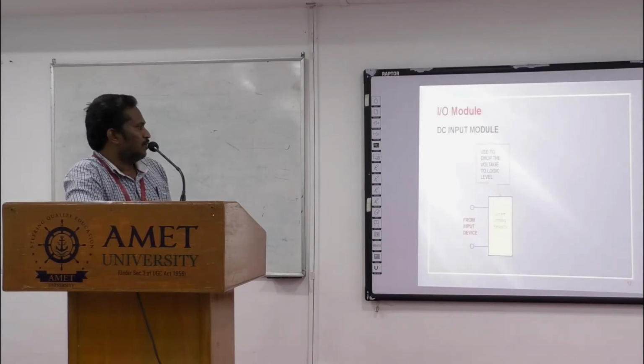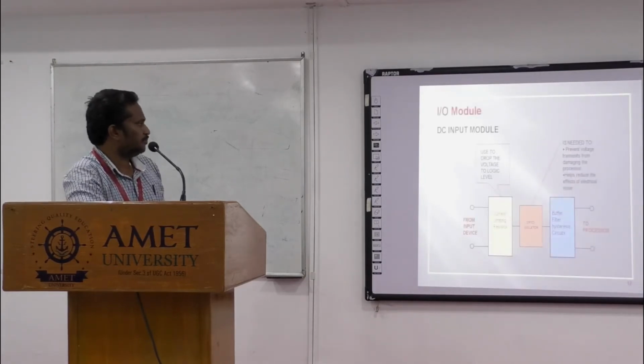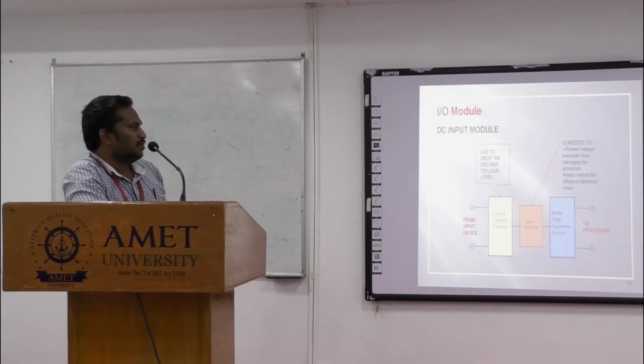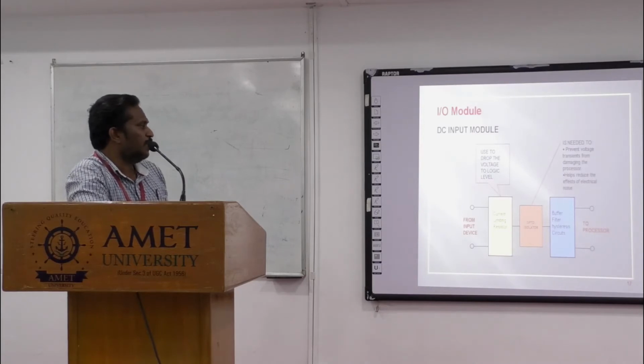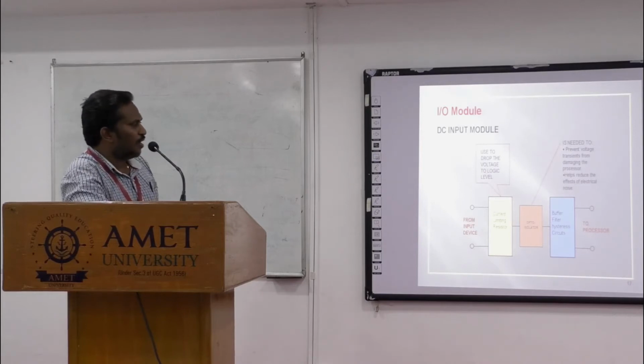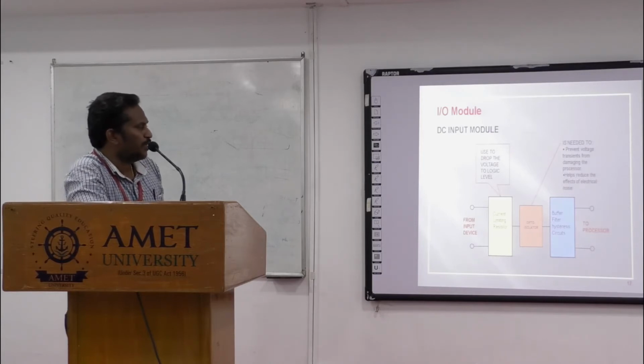DC input module. The DC input module will have three sections: a current limiting resistor, an opto isolator and a buffer unit. Here the current limiter resistor is for limiting the input current from the input device. The opto isolator acts as an isolating device between your CPU and the input device. In case of any fault in the input device that may affect your CPU, the opto isolator is used to prevent the fault current from entering into the CPU.